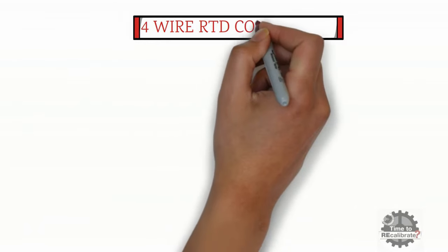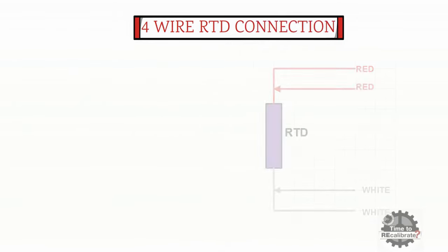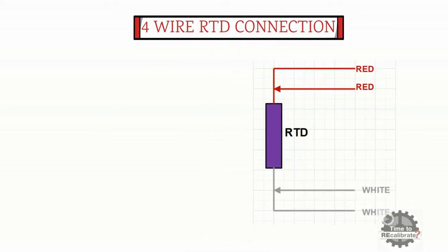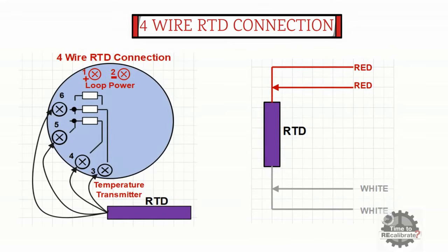In this section, I am going to show the 4-wire RTD connection with a temperature transmitter. As the name suggests, 4-wire RTD has 4 cables: 2 red cables and 2 white cables. To connect 4-wire RTD to the temperature transmitter, connect one red cable to terminal number 5 and another red cable to terminal number 6. After this, connect one white cable to terminal number 3 and another white cable to terminal number 4 of the temperature transmitter. Once done, turn on the loop power supply and check the reading on the display.